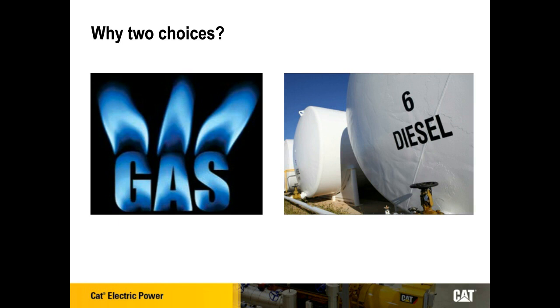They used our sizing software, SpecSizer, to evaluate the loads on both gas and diesel generator sets. Like most wastewater treatment facilities, it had some large motors resulting in large starting KVA requirements. After the sizing and site evaluation, diesel still made the most sense for this customer. The diesel generator's capability to pick up these large motors made the difference, and they were comfortable going with diesel after evaluating both fuel types.